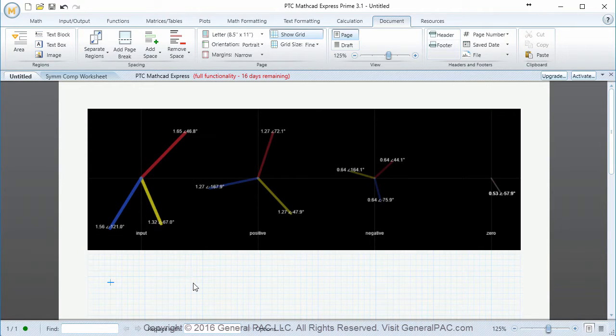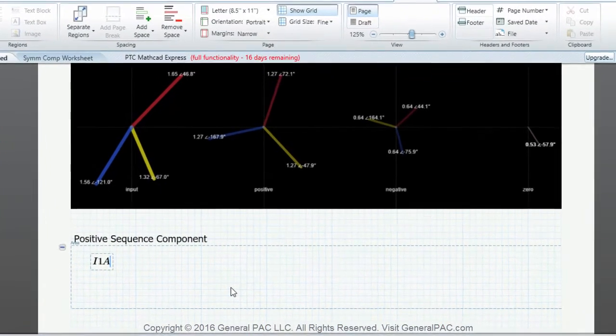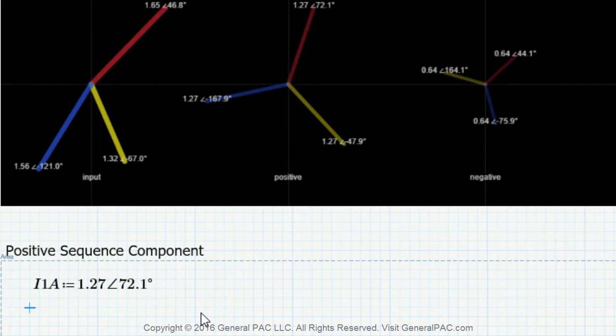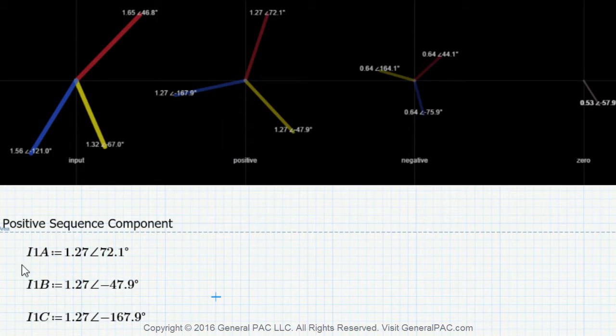Let's define our symmetrical component phasors. The positive sequence component for phasor A is equal to 1.27 at the angle of 72.1 degrees. The positive sequence component for phase B is equal to 1.27 at the angle of negative 47.9 degrees. And the positive sequence component for phase C current is equal to 1.27 at the angle of negative 167.9 degrees. So now we've defined the positive sequence component.